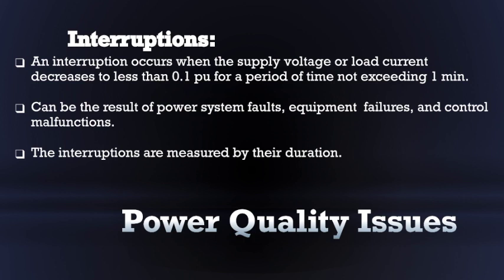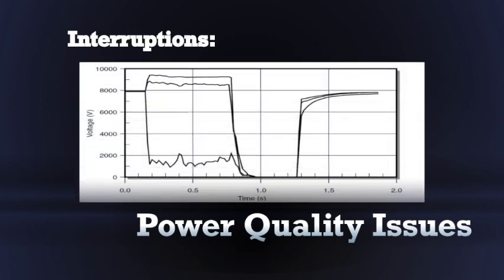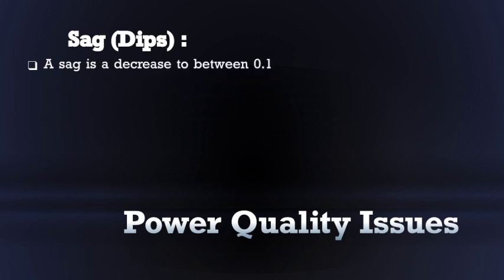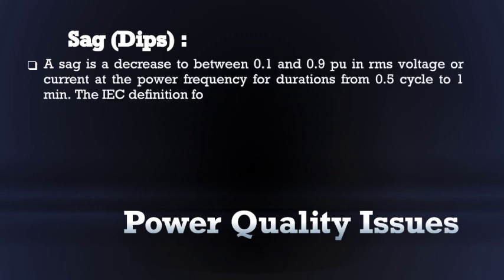Some interruptions may be preceded by a voltage sag. The figure shows such a momentary interruption during which voltage on one phase sags to about 20% for about 3 cycles and then drops to 0 for about 1.8 seconds until the recloser closes back. Now the second category of short duration voltage variation, known as sag. A sag is a decrease between 0.1 and 0.9 per unit in RMS voltage or current at the power frequency for durations from 0.5 cycle to 1 minute.